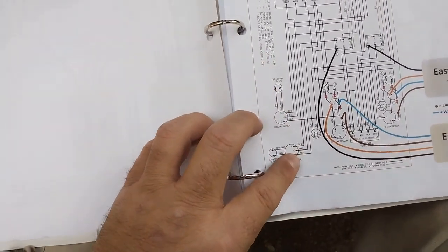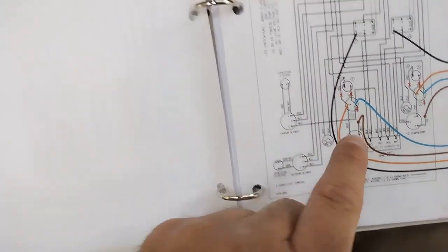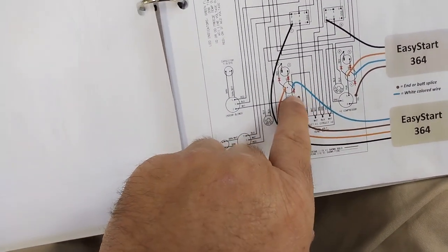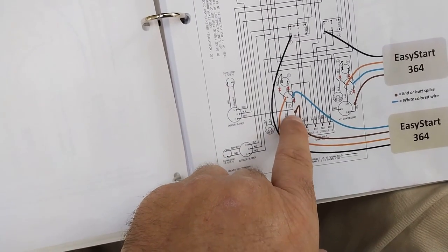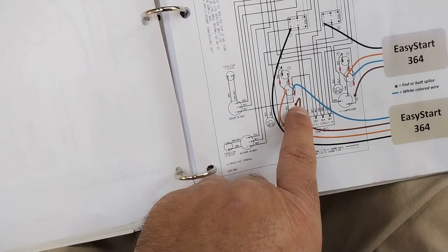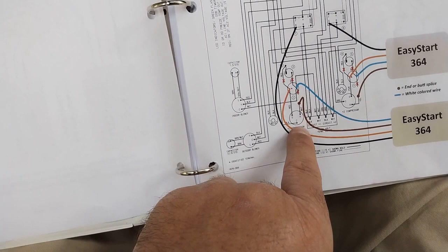Go back to the Easy Start instructions. Compressor one's the one we're doing first. The brown wire on here. We're going to cut the white wire that would go to the compressor. We're going to tie into the brown wire.